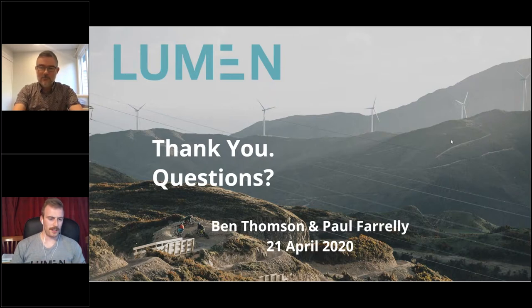How straightforward is it to work out the economics of replacing a condensing gas boiler installed only 3 years ago with a hot water heat pump at a public pool? That's a really good one. Relatively straightforward. There's a few things you need to consider. Obviously the heat pump is relatively expensive. The thing that can really get you is the electrical capacity increase required. And that's not just from the distribution transformer, but also in the local area and inside the building. So you need to talk to your network company first of all.